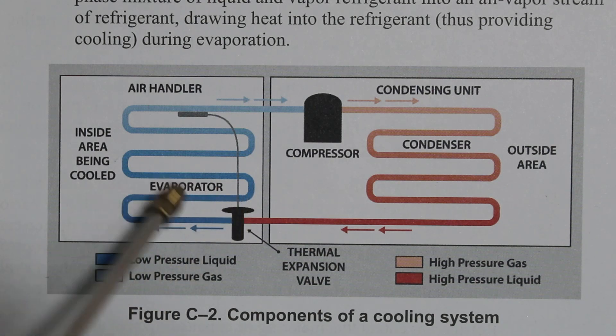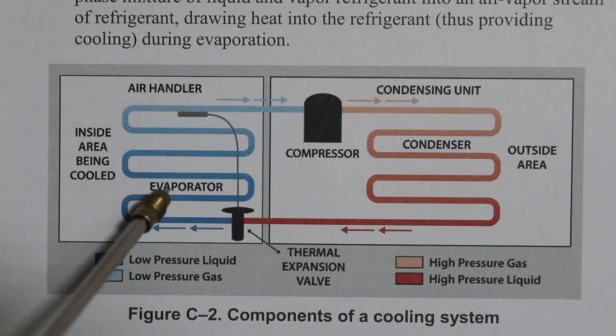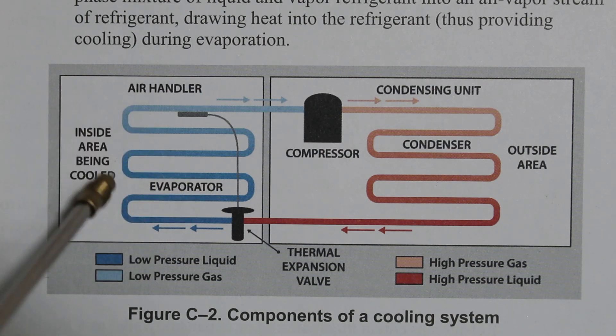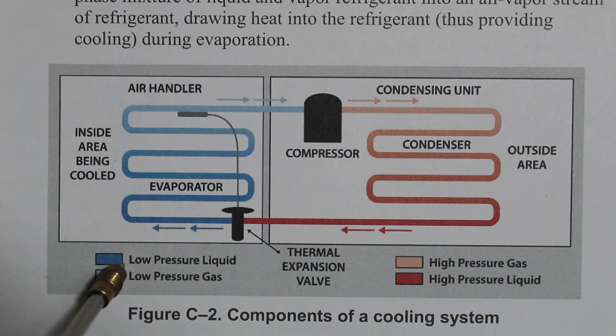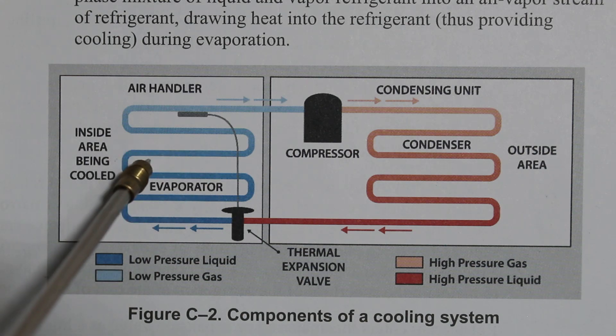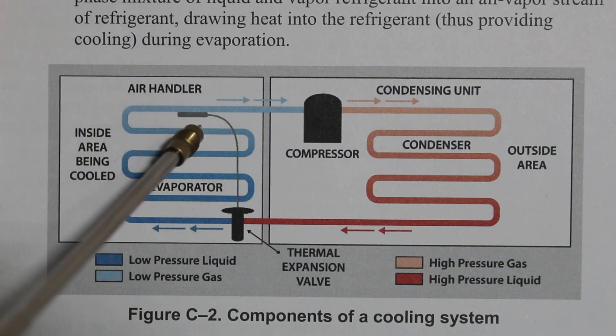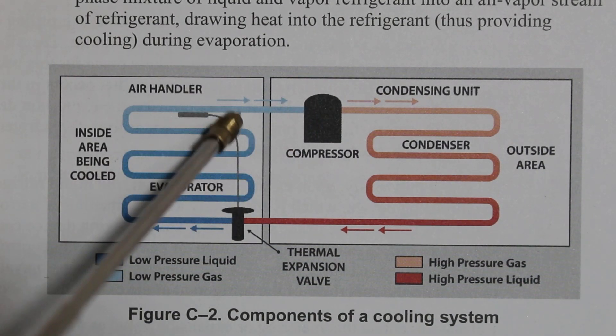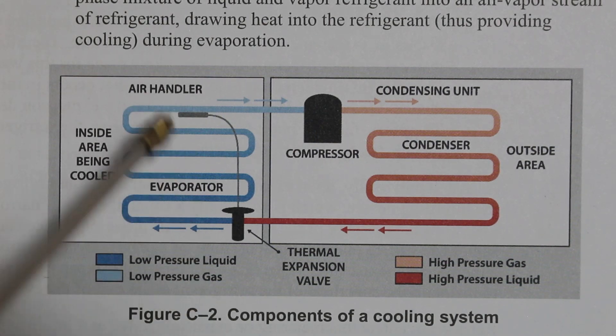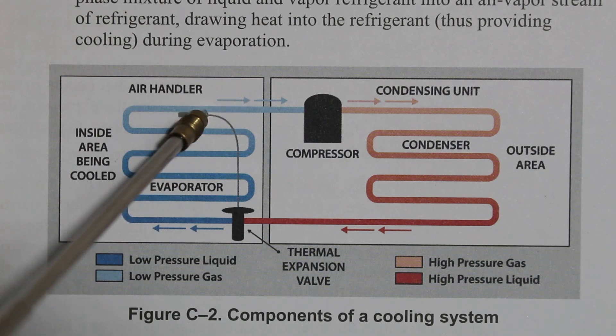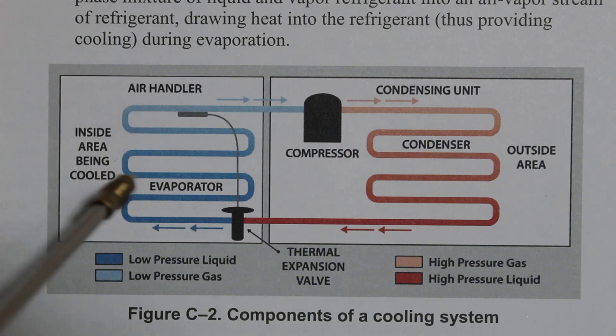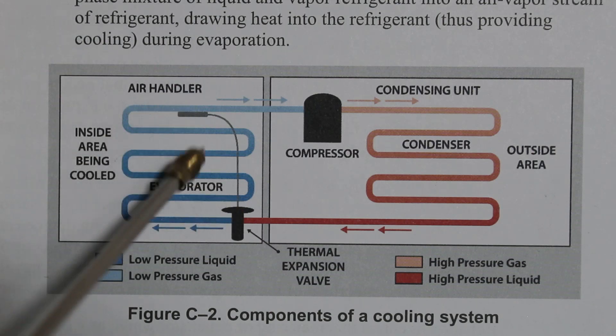Refrigerant continues down the cycle and we enter our fourth major component — the evaporator. Our evaporator is a coil just like our condenser, made out of copper with aluminum fins alongside a fan which blows air across it. In the evaporator we absorb heat, compared to the condenser where we reject heat. We enter as a low pressure liquid, and at about midpoint our refrigerant is saturated and we have latent heat of vaporization — a change of state from a liquid into a gas. The pipe leaving our evaporator and entering our compressor is known as our suction line, and on that suction line we are a low pressure, low temperature, superheated vapor.